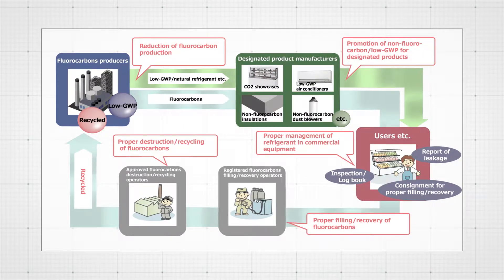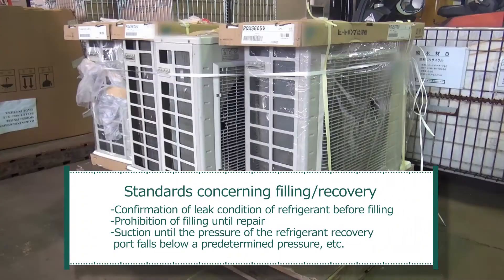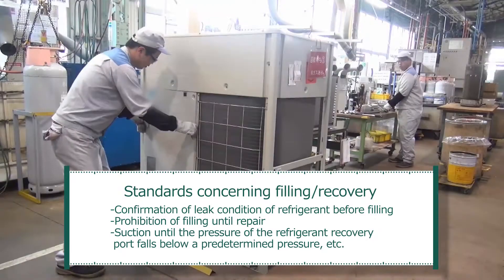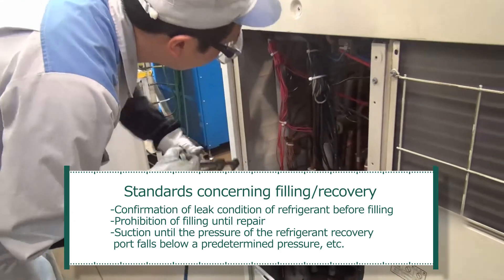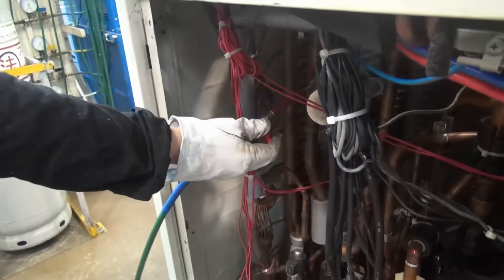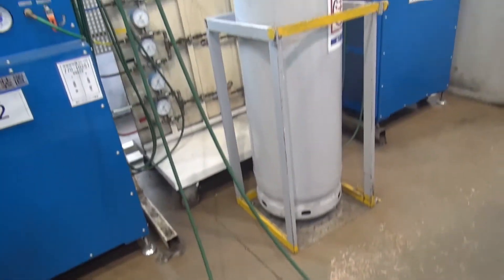Now let's move on to filling and recovery operators' efforts. When repairing, maintaining, or disposing of equipment, they may fill or recover fluorocarbon. This process must be done by a professional operator registered with prefectural authorities. Standards regarding filling and recovery include confirmation of the leak condition of refrigerant before filling, prohibition of filling until repair is completed, and suction until the pressure of the refrigerant recovery port falls below a predetermined pressure. Operators must follow these standards during filling and recovery.